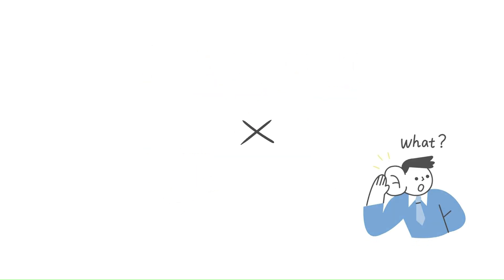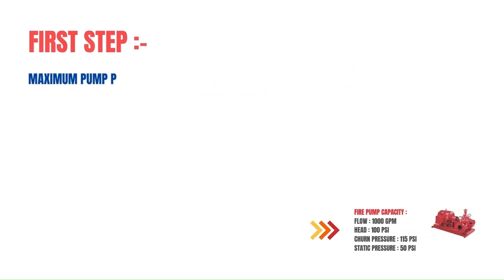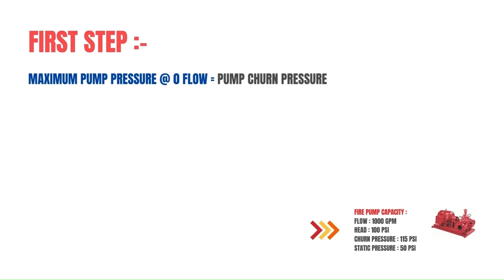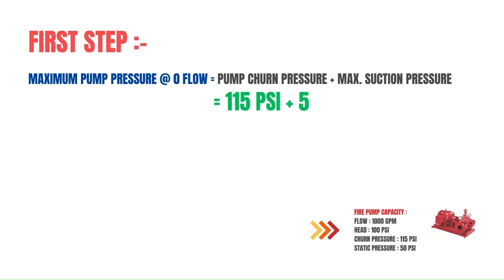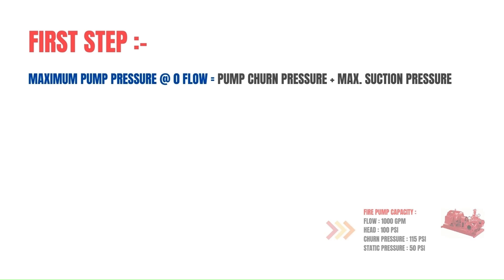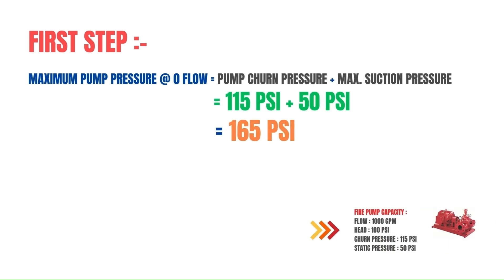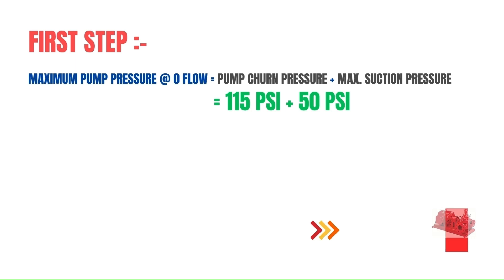The first step is knowing the maximum pump pressure at zero flow, or churn condition, which is calculated by adding the pump churn pressure with the maximum suction pressure. Using our data: 115 psi plus 50 psi gives us 165 psi. That completes the first step.